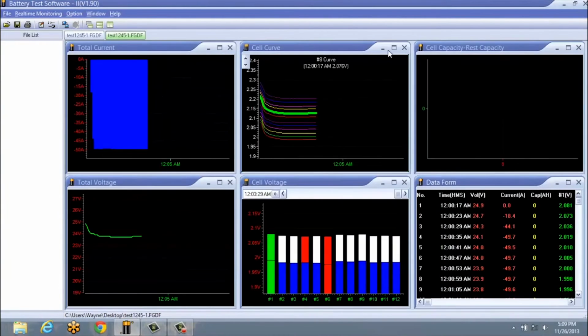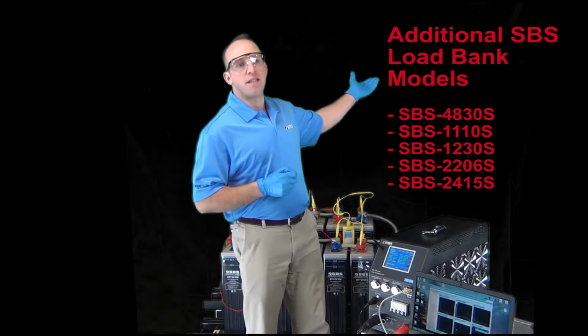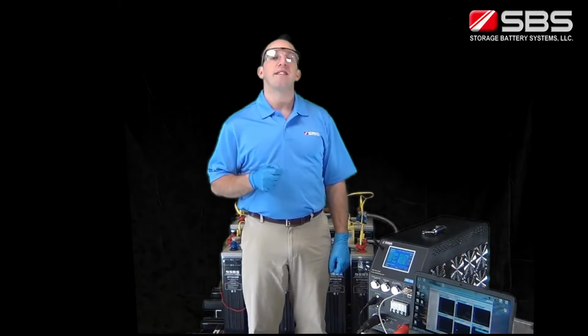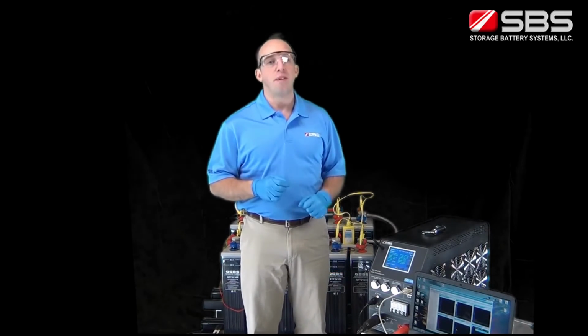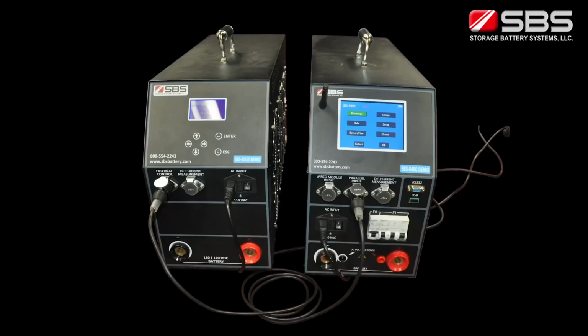It is important to use a correctly rated load bank unit while performing discharge tests. Here are all the different SBS load bank models. The SBS-8400 can be used in parallel with your existing load banks, as well as by simply adding the optional external 600 amp current clamp. The SBS-8400 load bank is a very accurate, reliable, and highly functional tool for testing and capturing test results. The SBS S-Series load banks can be operated in parallel with the SBS-8400 or another S-Series load bank of the same voltage range to increase the load current capacity of the system.